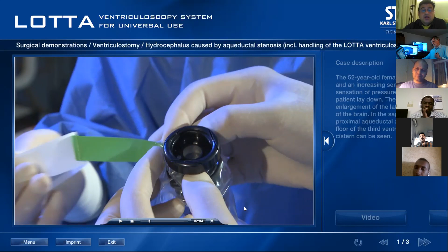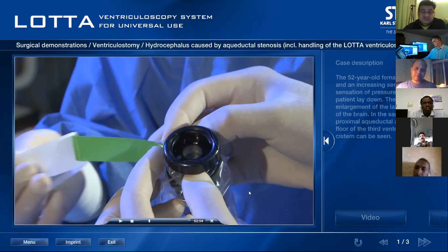And let's see further. Also, this sterile cover, many times in some small hospitals, they don't get these covers easily available. They use a cloth. So the sterile cloth is draped over this. The disadvantage is you cannot see. To get a true endoscopic anatomy image, the camera head buttons always have to face upwards. So if you use a non-transparent piece of cloth or any other thing over the camera head, you will never be able to know whether you are in the correct anatomical position or not.